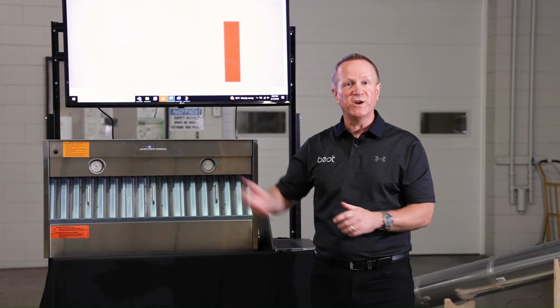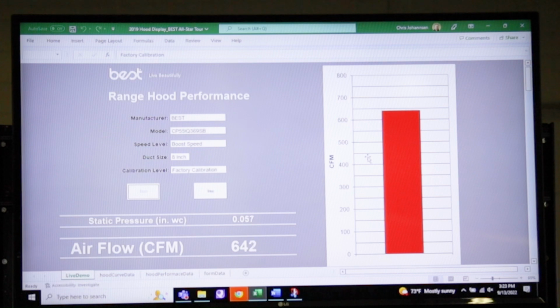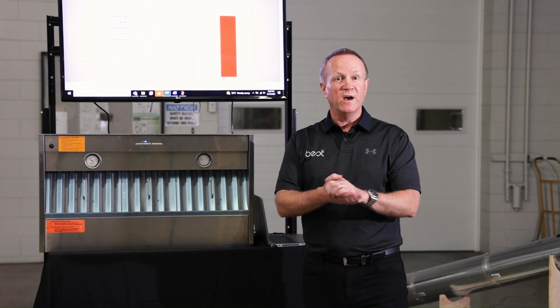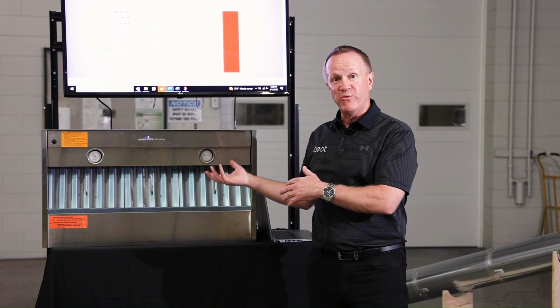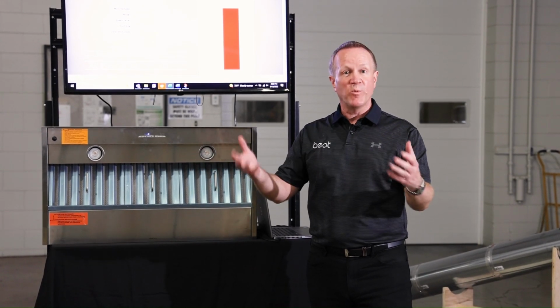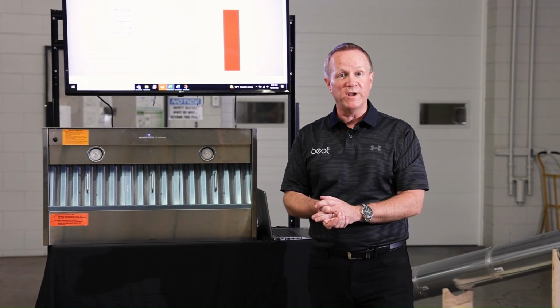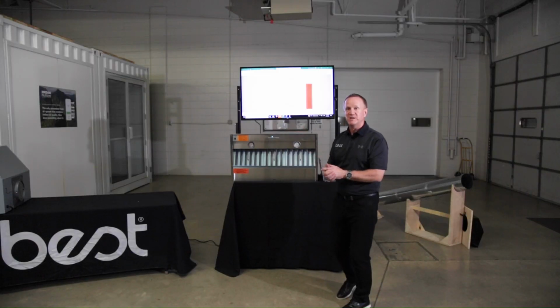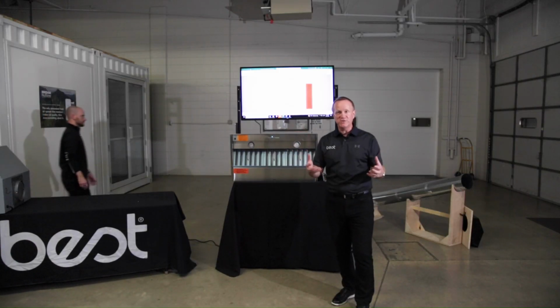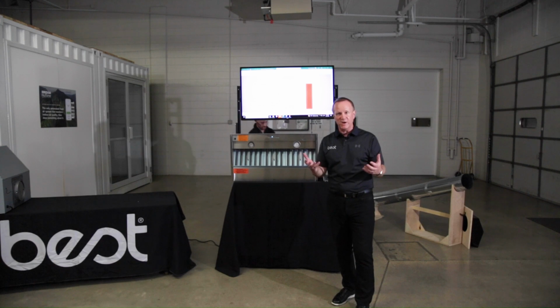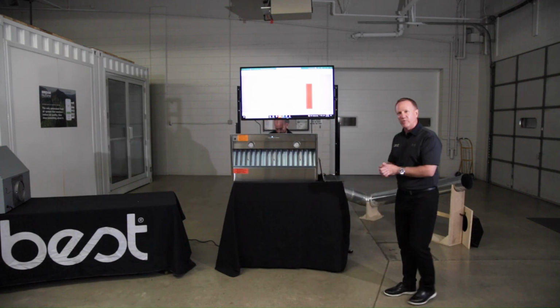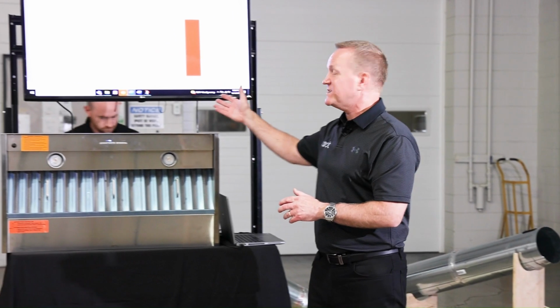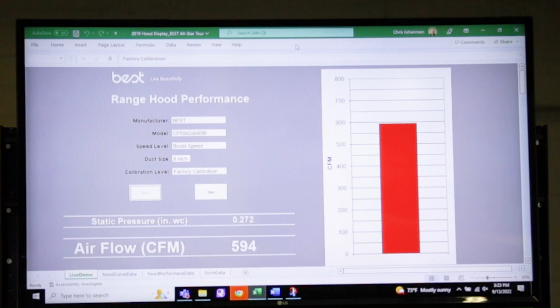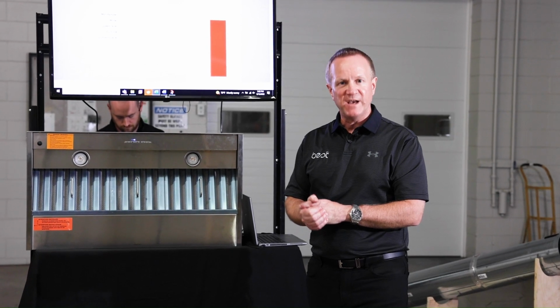So approximately 640 CFM. Again, you've worked with your client, you've spec'd out 600 CFM. So far with 4 feet of ducting, we're performing at about 640 CFM. So my colleague is gonna attach the additional ducting, giving us that 30 feet of ducting, and we'll see how we perform now. And you can see it has diminished the performance. We're down to about 595 to 600 CFM.